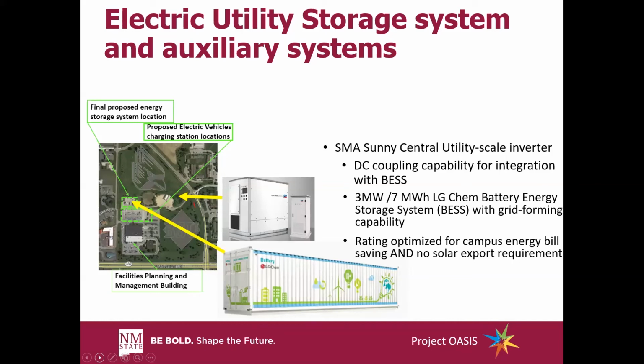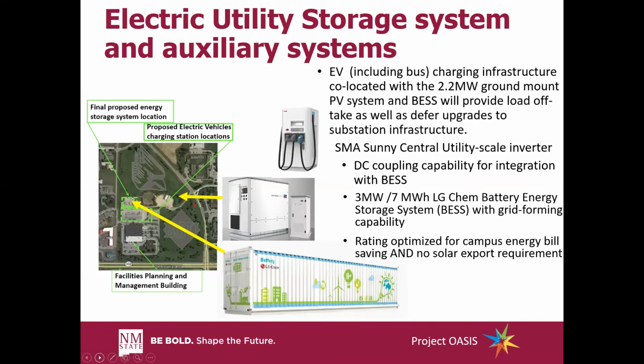We have verified that the LG Chem PCS is indeed capable of all the control functions we've specified for stacking of benefits. Indeed, the LG Chem PCS is capable of even more advanced fast response functions, such as operating in voltage source or current source mode, variable power factor operation, volt-var, and volt-watt support, which are beyond the scope of this project.